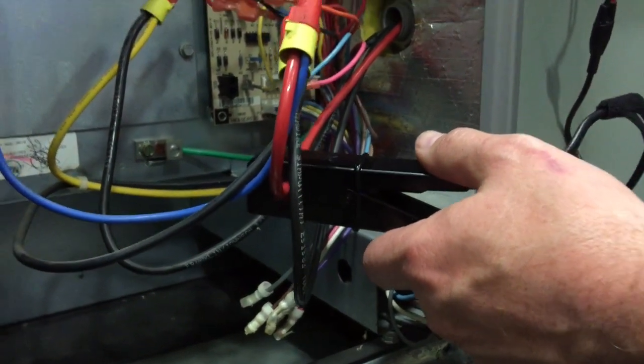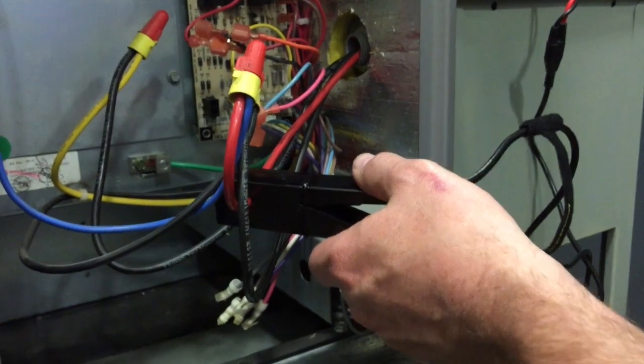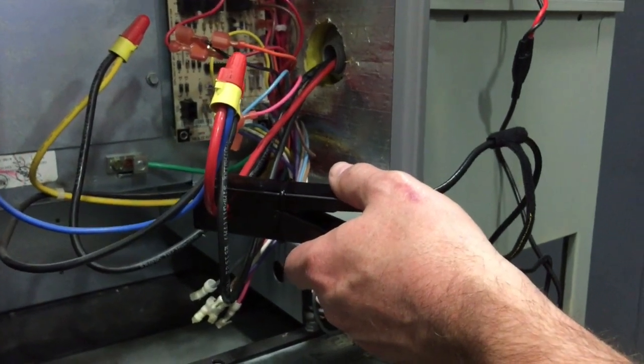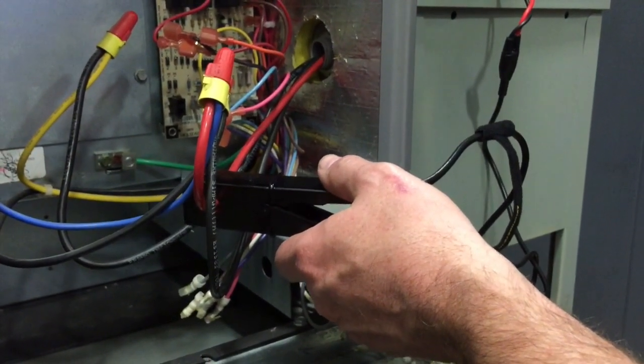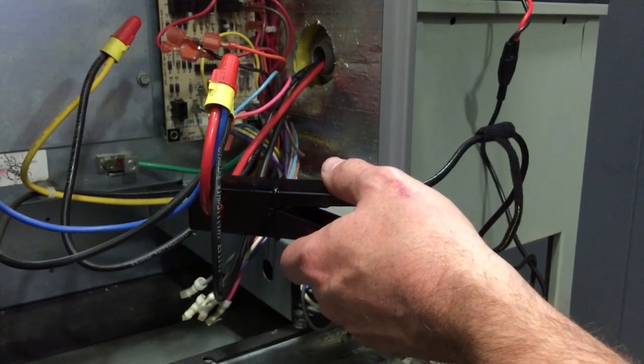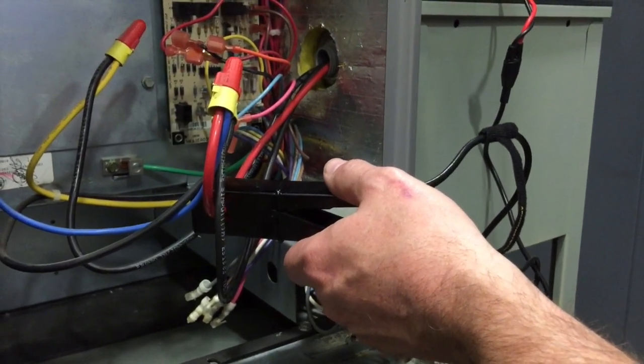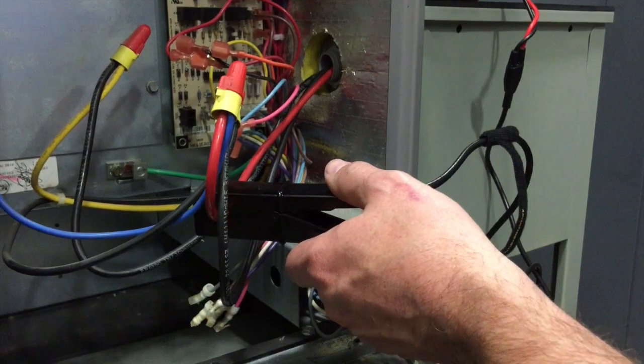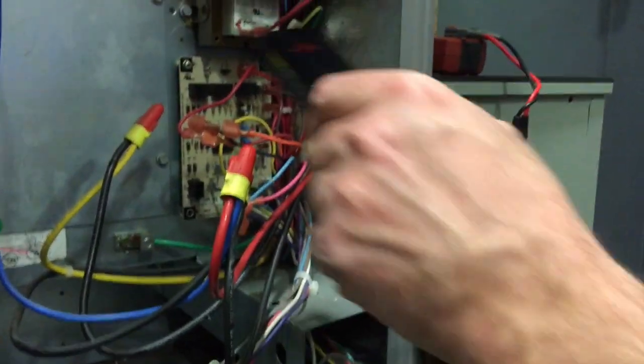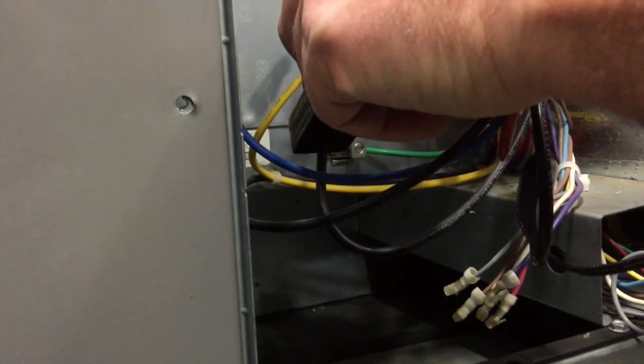Second current reading. And notice there's a small delay in here. We are waiting for the reading to stabilize. So we're actually running an algorithm in the background to make sure that enough readings have been taken that we get a good stable reading of current. Again, it's waiting for 0. Clip it onto the third lead coming in. And I have now all 3 legs of power.